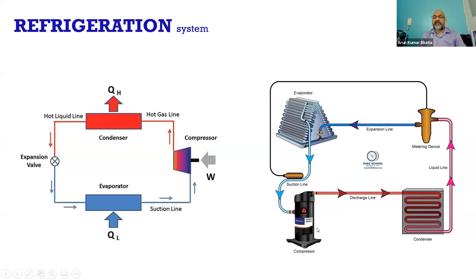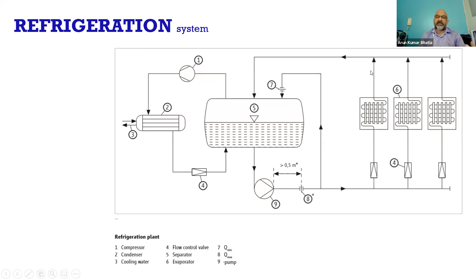Now this is another system, used for larger cold stores, called an ammonia pump, or other refrigerant. We can use carbon dioxide or any other eco-friendly refrigerant. Here too we have a compressor, condenser, and evaporators, but instead of an expansion system, we have a pump which is pumping the refrigerant into the evaporators. It's like in an air conditioning system where you pump water to fan coil units to generate a cooling effect. So in this system, we pump refrigerant in a liquid state to the evaporator, and the heat exchanging process is the same as the direct expansion system.